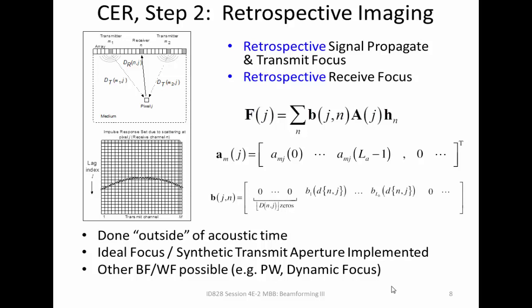The second step is that transmit and receive beamforming are linear operators on the impulse response. This A matrix includes the retrospective transmit waveforms, which in our case are just delayed Kronecker deltas. You could also use other waveforms retrospectively, like equalized pulse shapes to compensate for transducer bandwidth — that's discussed in our paper.